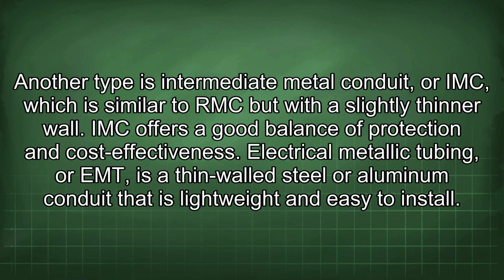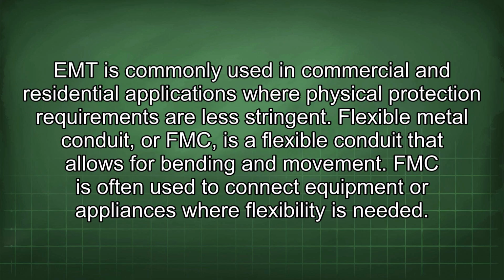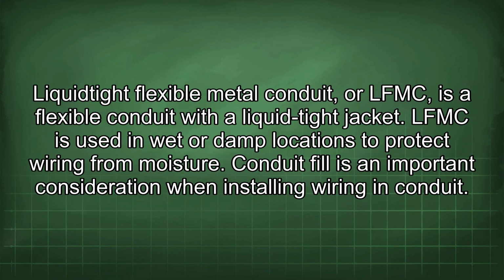Electrical metallic tubing, or EMT, is a thin-walled steel or aluminum conduit that is lightweight and easy to install. EMT is commonly used in commercial and residential applications where physical protection requirements are less stringent. Flexible metal conduit, or FMC, is a flexible conduit that allows for bending and movement. FMC is often used to connect equipment or appliances where flexibility is needed. Liquid-tight flexible metal conduit, or LFMC, is a flexible conduit with a liquid-tight jacket. LFMC is used in wet or damp locations to protect wiring from moisture.